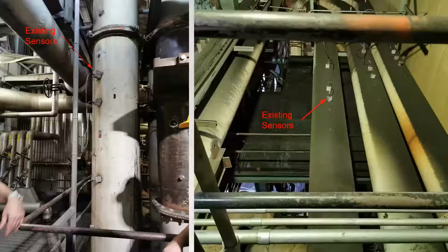Pictured here are some of the existing sensors at Huntington Power Plant. These sensors protrude into the coal flow and are worn away by abrasion in a matter of months. Replacing these sensors is both expensive and time-consuming. So many of the pipe flows are measured by hand using isokinetic sampling. PacifiCorp has asked us to develop a cheaper, more durable sensor.